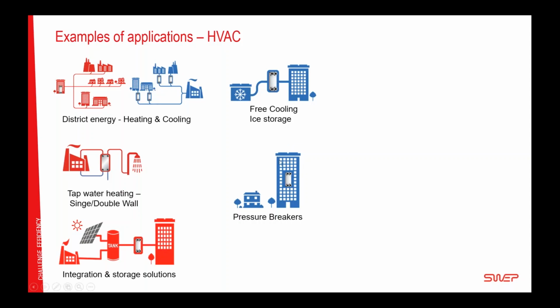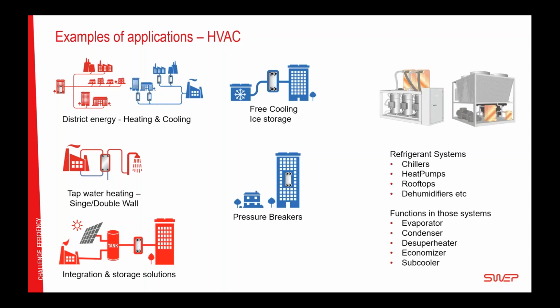Pressure breakers in tall buildings. When a building is very tall, the static pressure in the water tubes becomes too high and risks bursting the pipes. And if you have a heat exchanger, you divide that height and limit the pressure in the system. I know I'm going pretty fast here, but we will have a landing page. More common applications are in any type of refrigerant system, chillers, heat pumps, rooftop, dehumidifiers, anything where there is a refrigerant cycle and a compressor. And the functions that a brazed plate can do there is as an evaporator, condenser, which we'll actually look at in the SSP portion of this webinar, desuperheater, economizer, subcooler, suction gas heat exchanger, oil cooler for the compressor, etc.